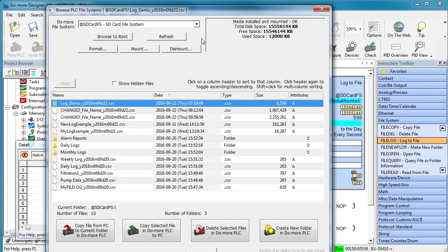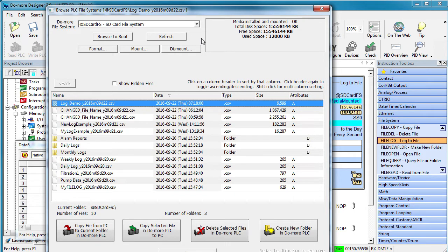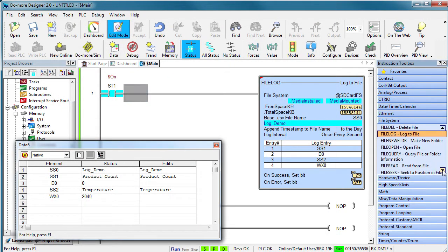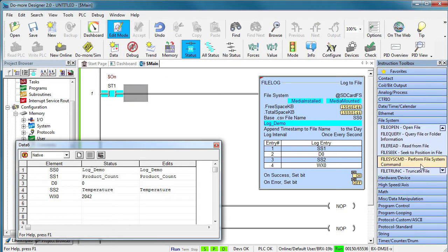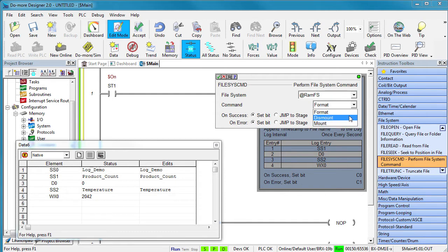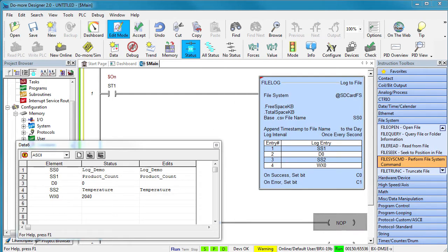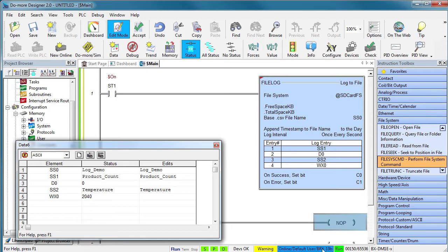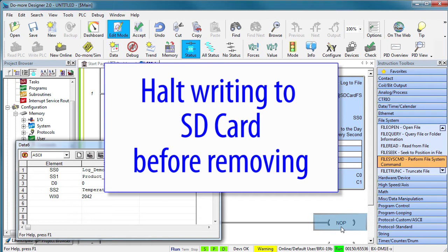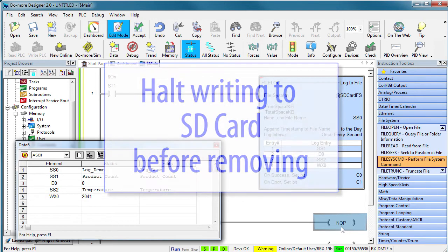The way around that is to provide this mount and dismount ability. Simply bring up this file browser and dismount the SD card before removing the card from the extension cable. Likewise when you plug the card in, hit mount to tell the BRX the new card has been inserted. Could you connect an HMI and have a button on it to mount and dismount the SD card? Sure. Just use the file system command in your ladder code to format, mount or dismount the SD card. Note that it's fully asynchronous. You just hit it with a rising edge – usually the HMI button press for example – and then wait for it to tell you it's done so you can tell the user it's safe to remove the SD card. Whether you are using an extension cable or not, please make sure you are not writing to the SD card when you remove it from the PLC.